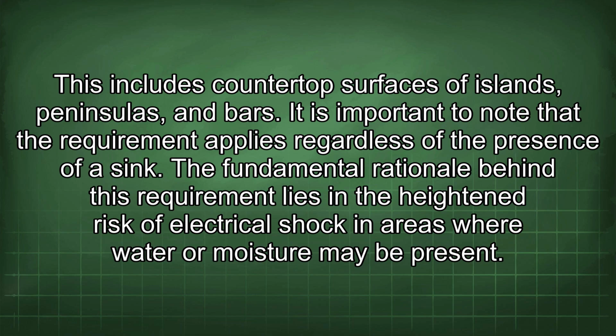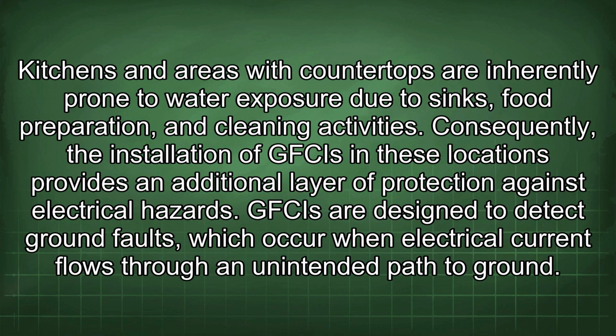The fundamental rationale behind this requirement lies in the heightened risk of electrical shock in areas where water or moisture may be present. Kitchens and areas with countertops are inherently prone to water exposure due to sinks, food preparation, and cleaning activities. Consequently, the installation of GFCIs in these locations provides an additional layer of protection against electrical hazards.